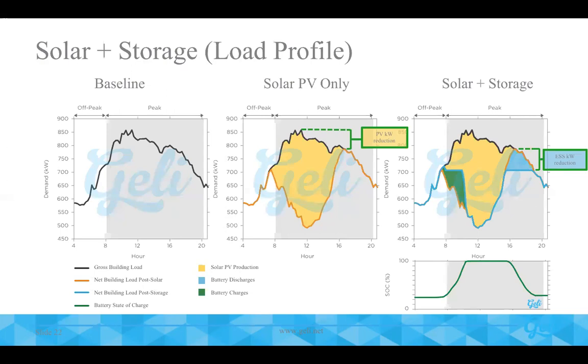If you think about each component's demand reduction capabilities, PV brings down the peak load about 100 kilowatts, and before, storage alone only brought down the load about 50 kilowatts. But now, because the load profile has been augmented by solar generation, storage is more effective in reducing that last bit of demand in the evening. Whereas before it only brought the peak from 850 to 800, now it's taking the shoulder hour peak from 800 down to 700 kilowatts. This doubles the effectiveness of the energy storage.